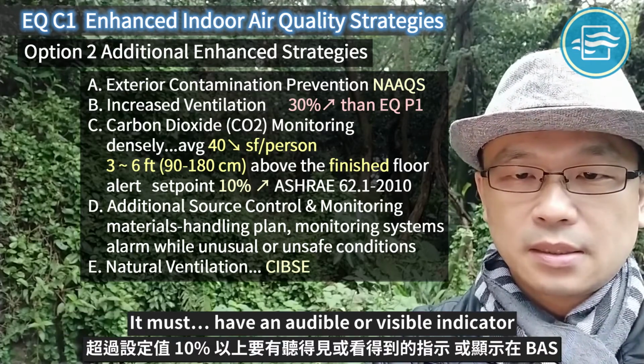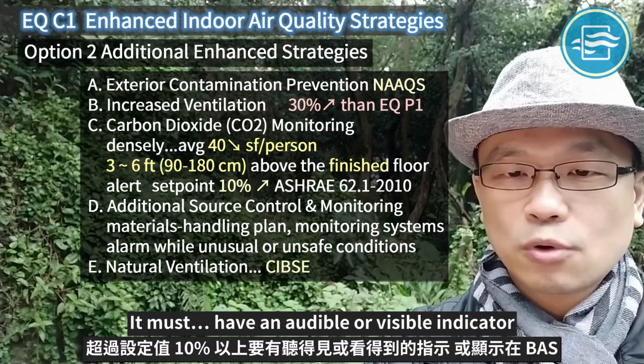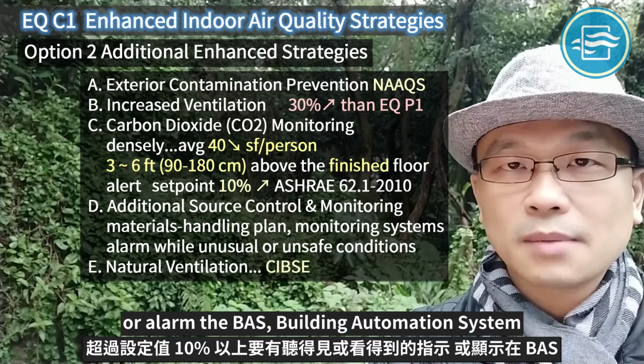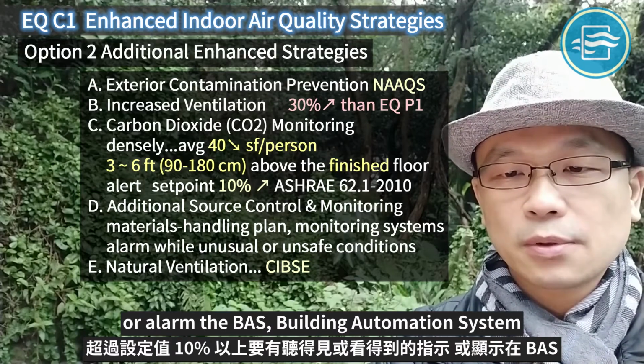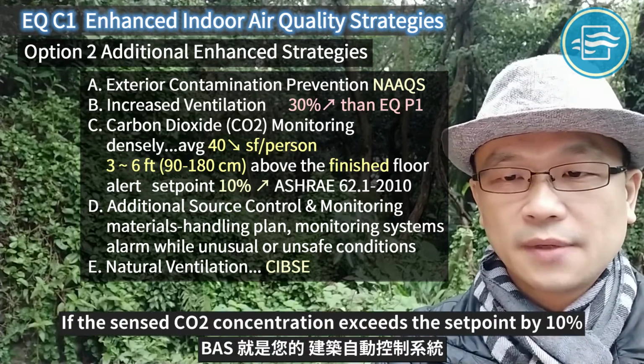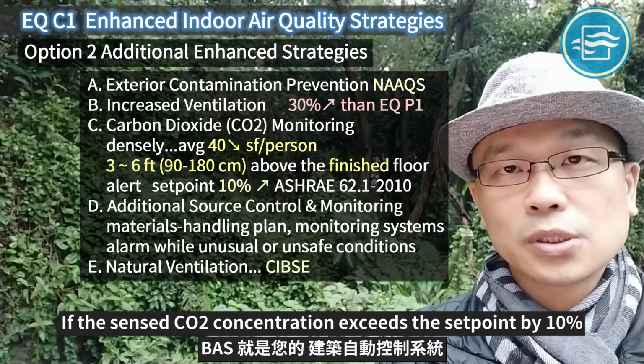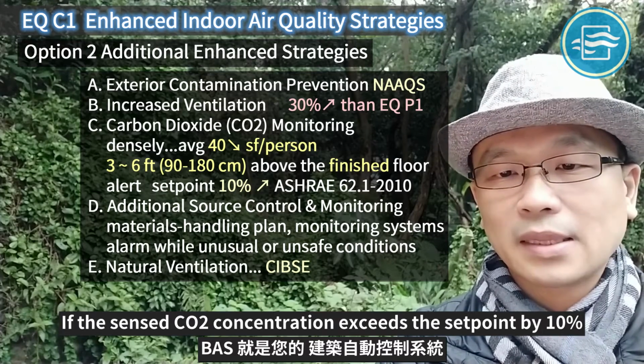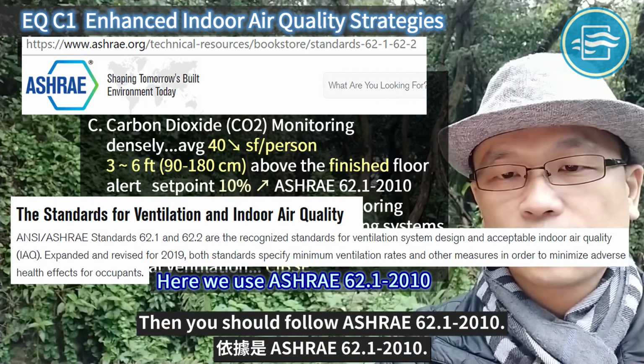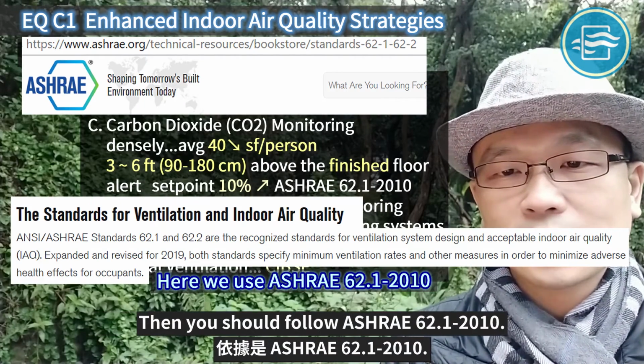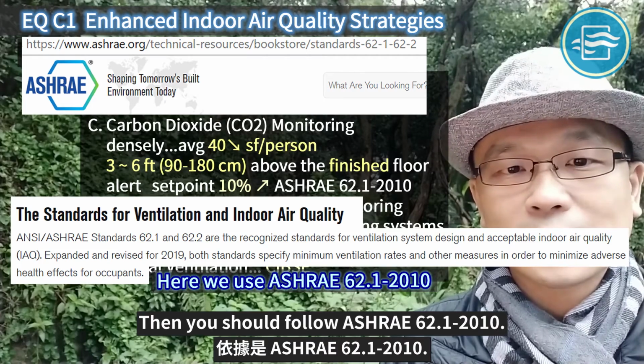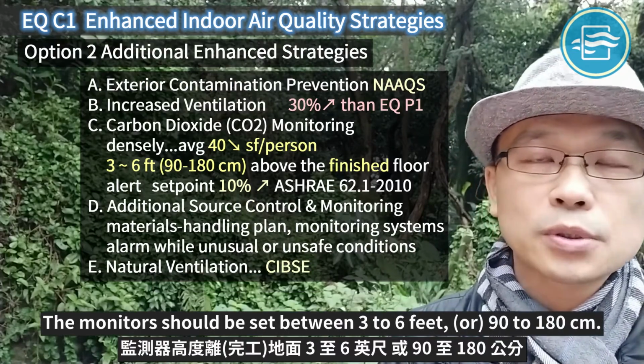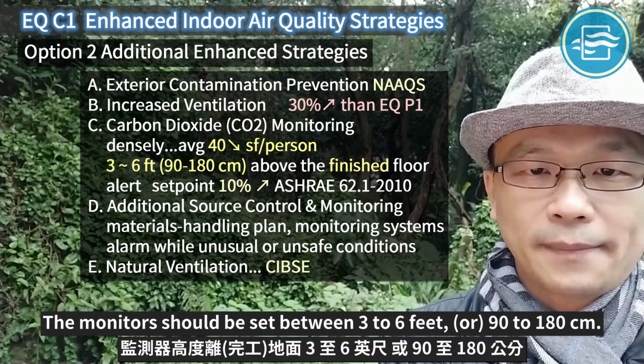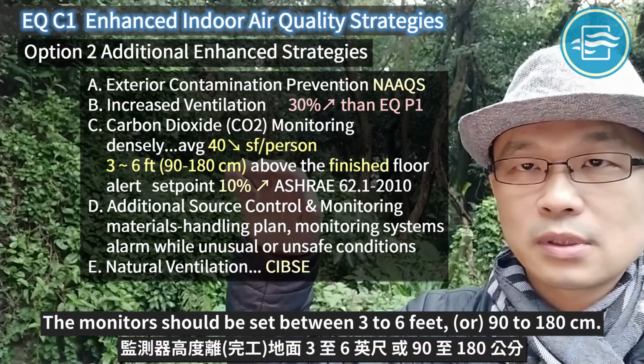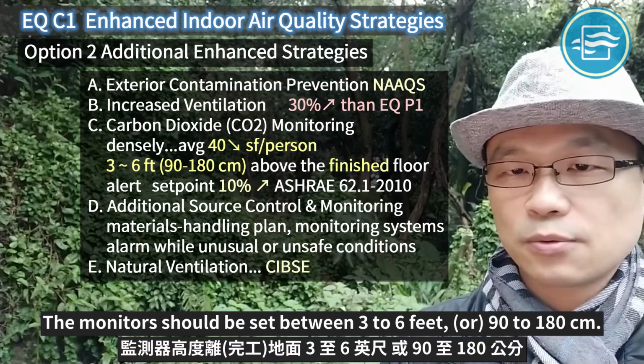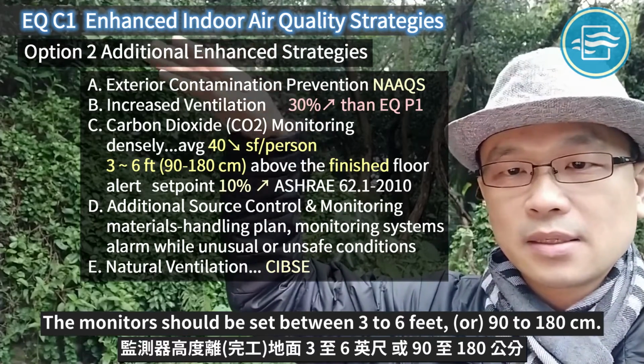It must have an audible or visible indicator or alarm on the BAS, building automation system, if the sensed CO2 concentration exceeds the set point by 10%, and it should actually follow 62.1 2010. The monitors should be set between 3 to 6 feet, 90 to 180 centimeters.